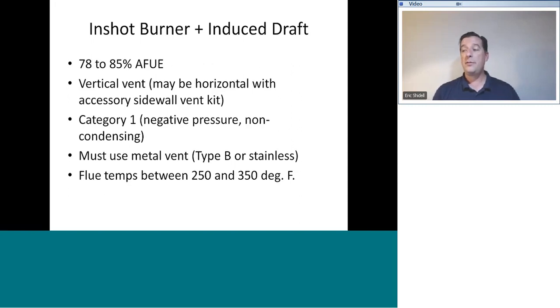Now, I said they're vertical vent. Some of these Category 1 induced draft appliances can be horizontal vented with a special horizontal vent kit. What that entails is there's a special blower located on the outlet of the flue near the outside wall to draw those combustion products horizontally through the vent and deliver them to the outdoors. That horizontal vent kit must be authorized and approved by the furnace manufacturer. You cannot just walk into a house and go, oh yeah, we'll just run that vent right through the sidewall. We'll just go and get a Field Controls or Tjernlund sidewall vent kit, no problem.